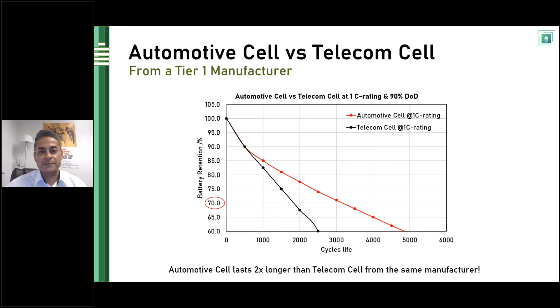Some manufacturers say they can charge the battery at a 1C rating, which is true, and you can do that with a Fortress Power battery too. But the way our batteries are spec'd, we recommend not charging or discharging beyond a 0.5C rating. Going beyond that greatly impacts the cycle life of the battery, and this doesn't depend on the company or manufacturer, these are science-based numbers.